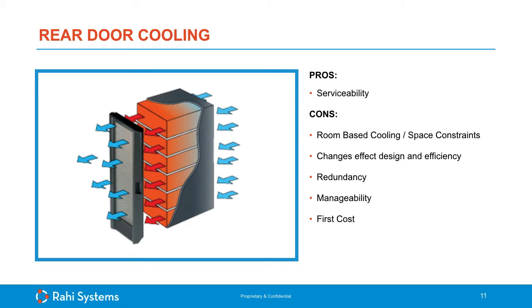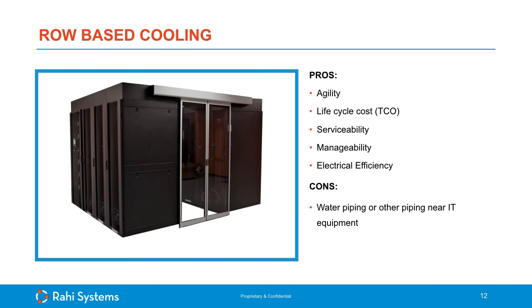However, the challenges are around redundancy. There's typically one rear door cooler per rack, so again, hard to design around an N+1 or 2N. Also, in large deployments, the first cost can be considered much higher, and you're managing multiple connections. Managing multiple water and refrigerant connections can also present a problem. Let's take a look at row-based cooling, which is what we're going to be really focusing on today.